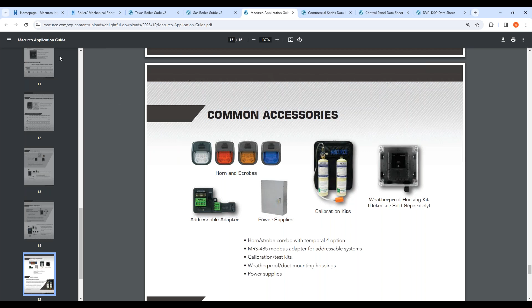There's something called a drift, where sensors over time can drift a little bit, and the calibration just brings it back to normal. So if anybody has questions on calibrations or testing, anything of that nature, this is a very, very large market right now. It's probably one of the more talked about markets in terms of gas detection as a whole, is just keeping the products updated, because it's no longer a set it and forget it scenario.